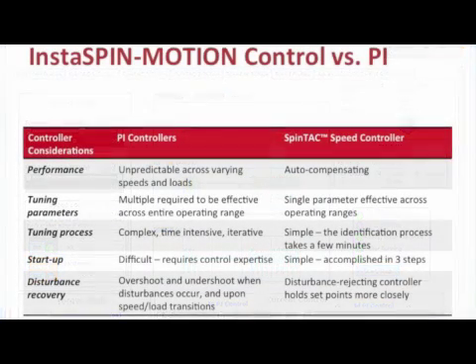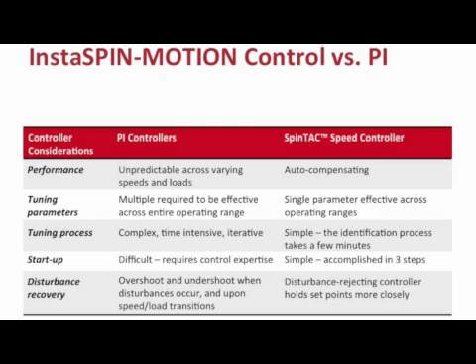This means that the PI controller requires multiple sets of tuning parameters. With PI control, you'll need to invest more time in identifying all of the variables for your application, tuning sets for each combination of variables, and doing validation testing. Bottom line: PI tuning requires a bigger investment.